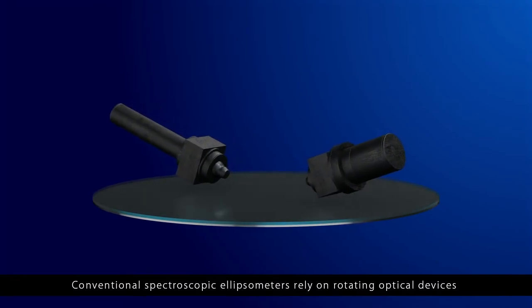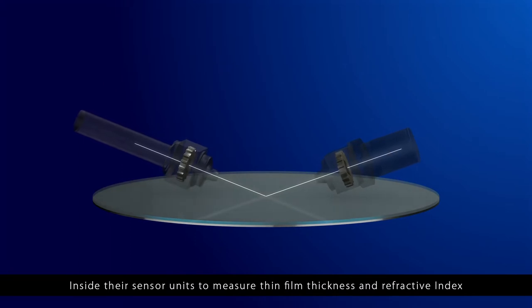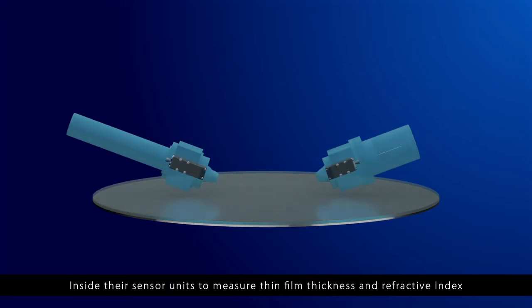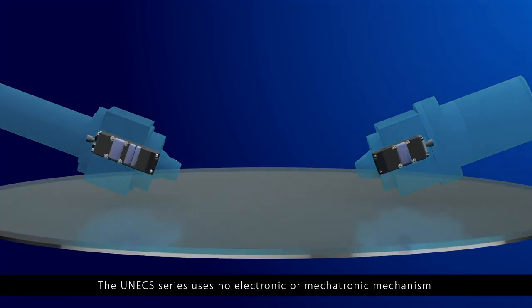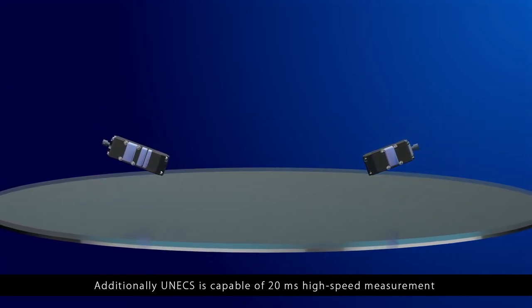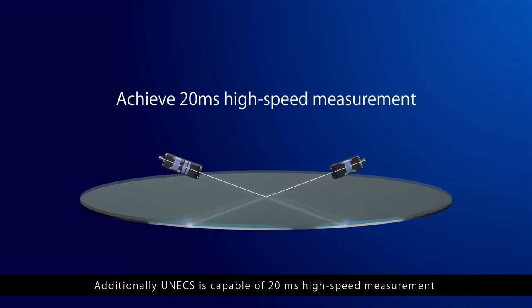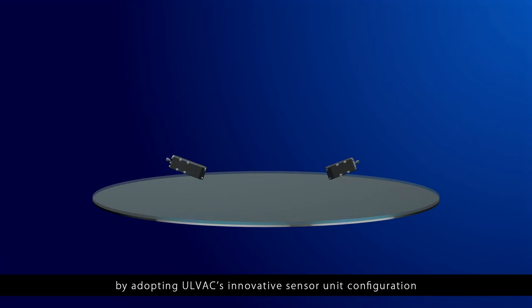Conventional spectroscopic ellipsometers rely on rotating optical devices inside their sensor units to measure thin film thickness and refractive index. The UNECS series uses no electronic or mechatronic mechanism, making them compact and maintenance-free. Additionally, UNECS is capable of 20 millisecond high-speed measurement by adopting ULVAC's innovative sensor unit configuration, which uses fixed optical devices only.